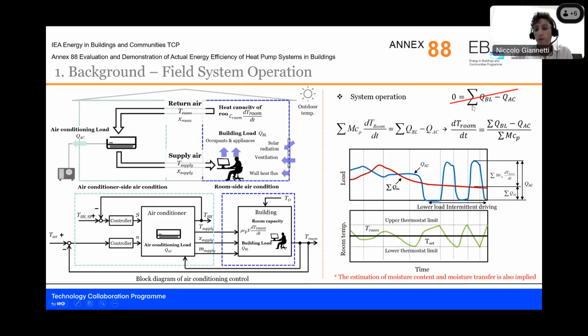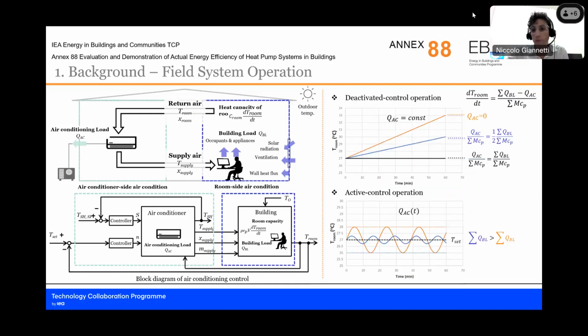Most of the time, these systems do not operate in steady state operation, where cooling capacity, in the case of an air conditioner, is perfectly balancing the building load. But in practice, these two quantities might have an imbalance, and any imbalance results in an indoor condition variation, for example, temperature or humidity. This variation, or the rate of this variation, is dependent not only on the magnitude of the imbalance, but also on the characteristics of the building, so the thermal inertia of the building. So how slowly or how fast the temperature is changing in relation to this imbalance between capacity and load. Here is just to exemplify what I just said.